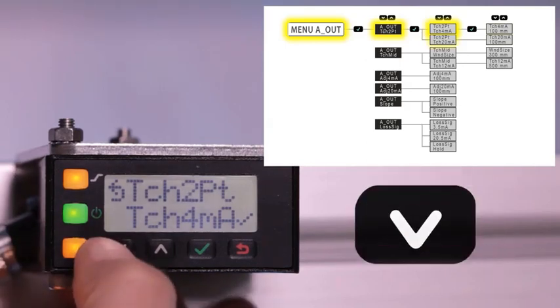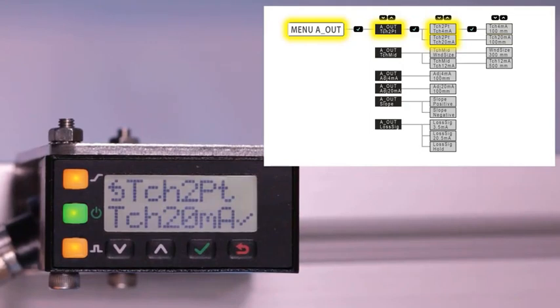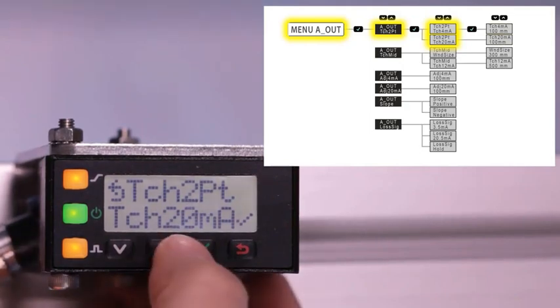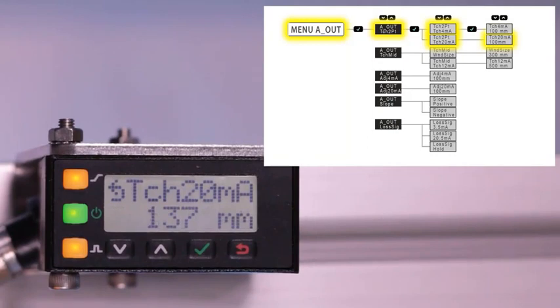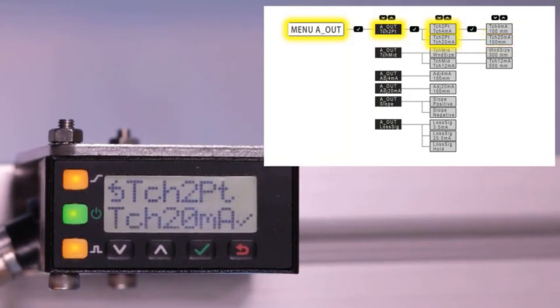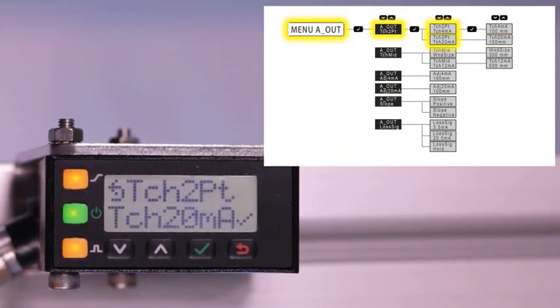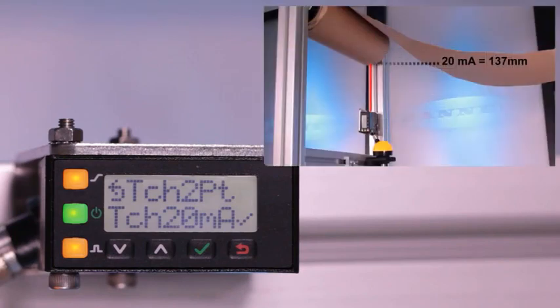Click down to teach 20 milliamp. Present a target, click enter, and the sensor will automatically teach the 20 milliamp point based on the position of the outer diameter of this roll. After a successful teach, the sensor will flash the value taught. So the 20 milliamp point is now located at 137 millimeters.